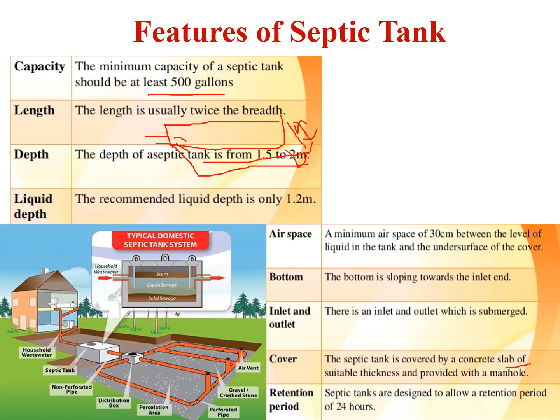Air space: a minimum air space of 30 centimeters between the level of liquid in the tank and the underside of the cover. The bottom is sloping toward the inlet, meaning the floor slopes toward the inlet. Cover: the septic tank is covered by a concrete slab of suitable thickness and provided with a manhole. The septic tanks are designed to allow a retention period of 24 hours.